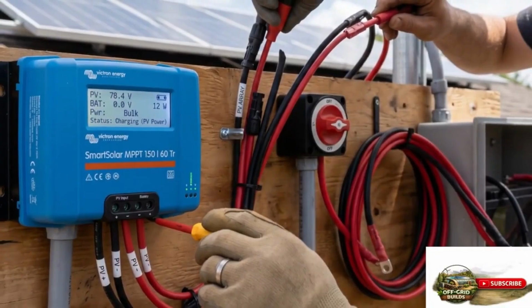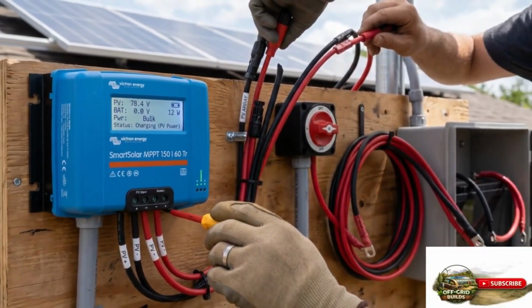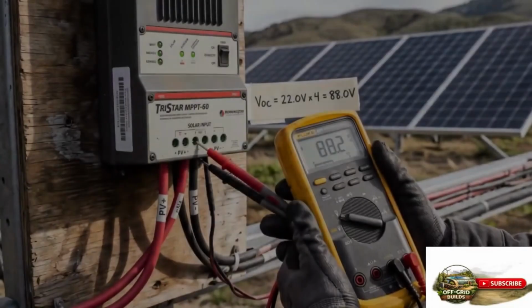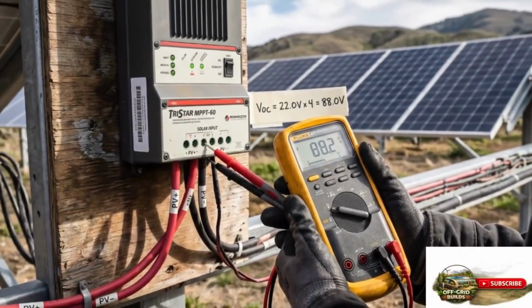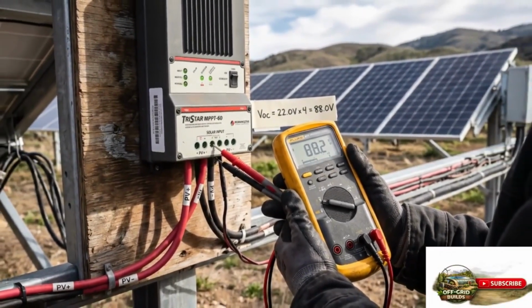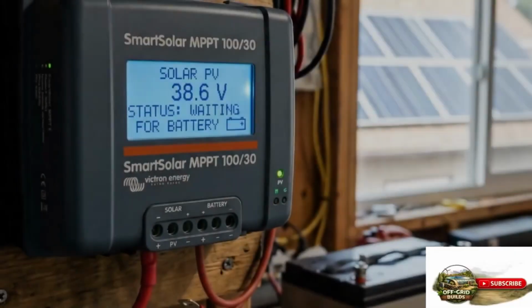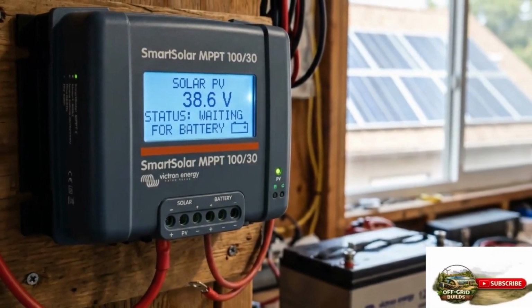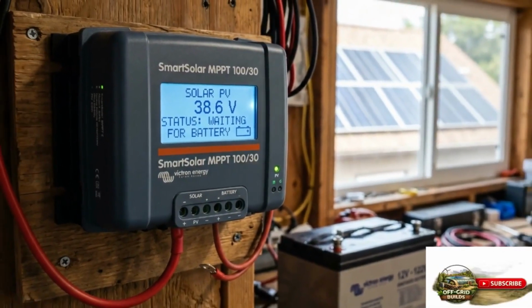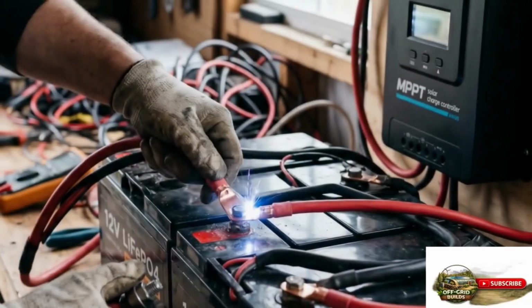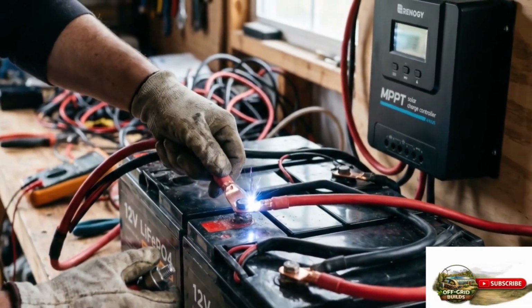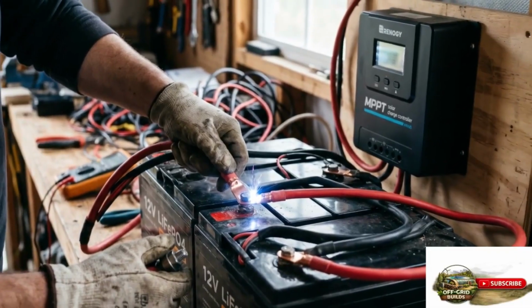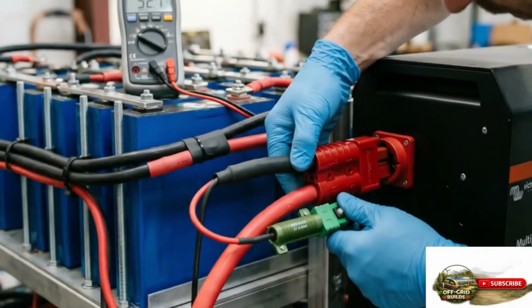Verify all equipment is mounted securely and all conduit and wiring is routed and secured correctly. Verify that grounding connections are complete throughout the system. With the battery bank still isolated, connect the solar array to the charge controller and verify that the charge controller powers on correctly and shows the expected array voltage. Any unexpected behavior at this stage should be investigated before proceeding.